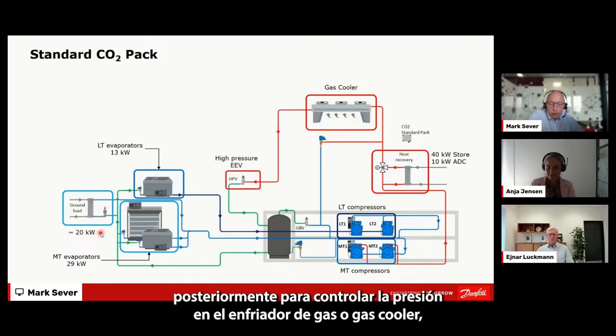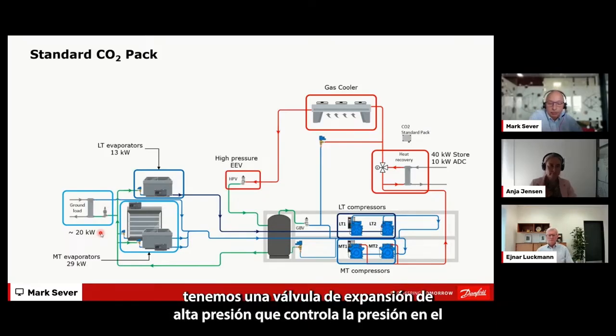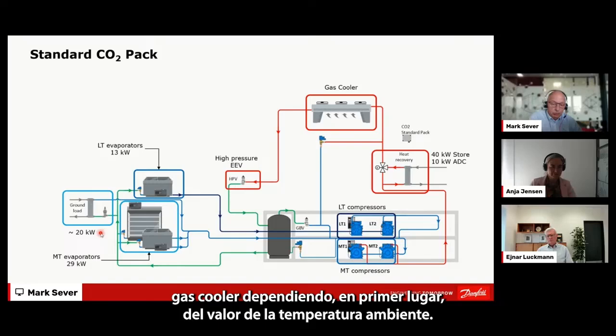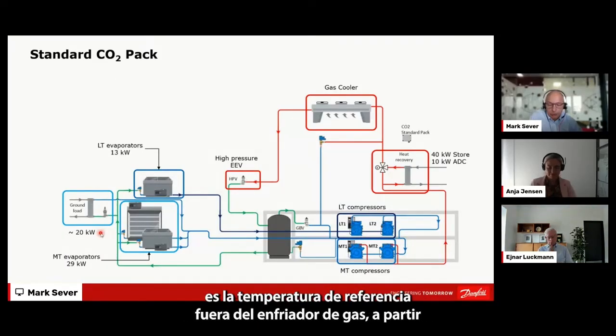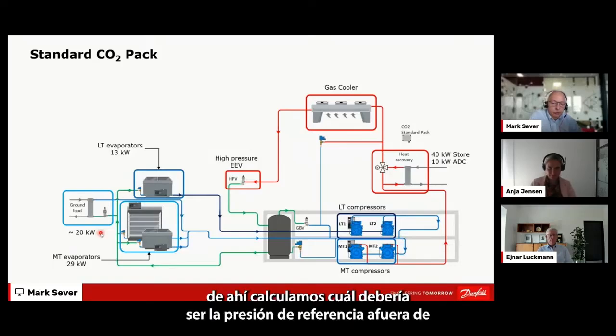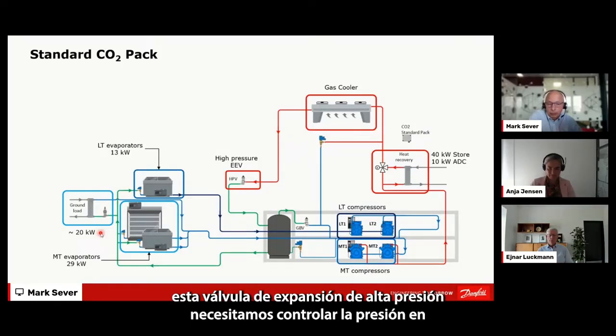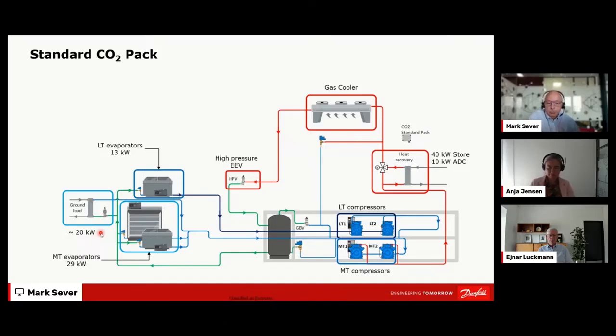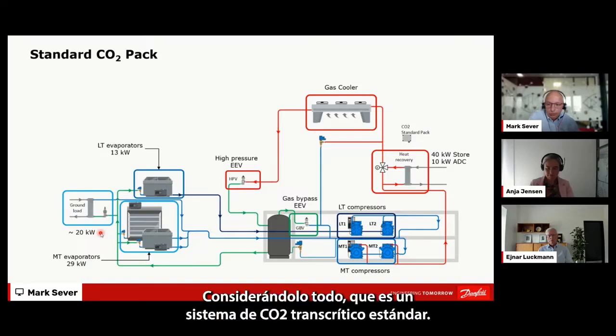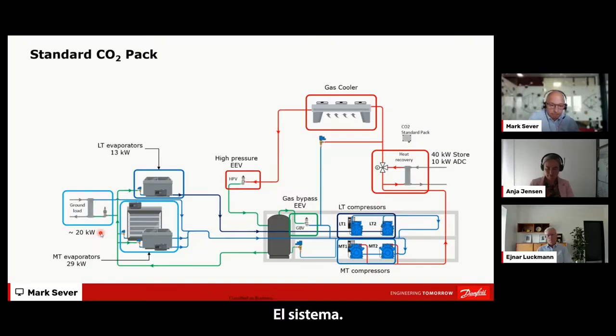Then to control pressure in the gas cooler, we have a high pressure expansion valve, which is controlling pressure in the gas cooler depending, first of all, on the ambient temperature measurement. From the ambient temperature we define the reference temperature out of the gas cooler. From that we calculate what the reference pressure in the gas cooler should be. This is something specific to CO2 systems. After this high pressure expansion valve, we need to control pressure in the receiver, which some people also call a separator. Here we control this pressure by using a gas bypass valve. All in all, this is a standard CO2 transcritical system.